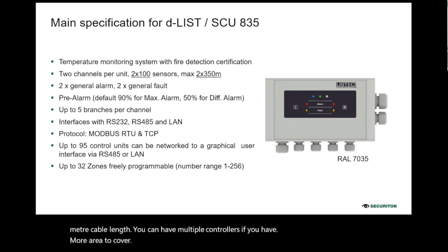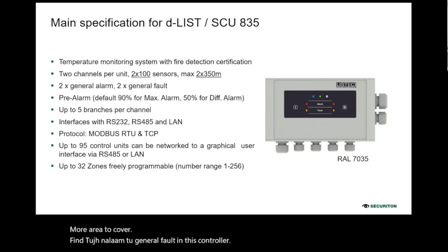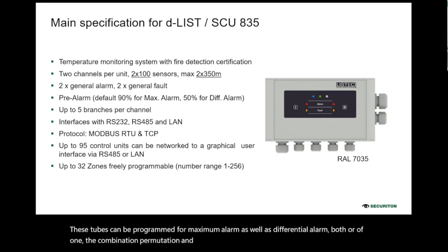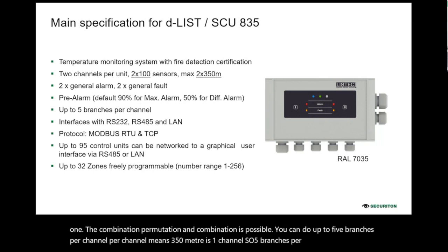You find 2 general alarms, 2 general faults in this controller. 3 alarms are also possible. These can be programmed for maximum alarm as well as differential alarm, both, or one of them. The combination, permutation and combination, is possible. You can do up to 5 branches per channel. Per channel means 350 meter is one channel. So 5 branches per channel is always possible.